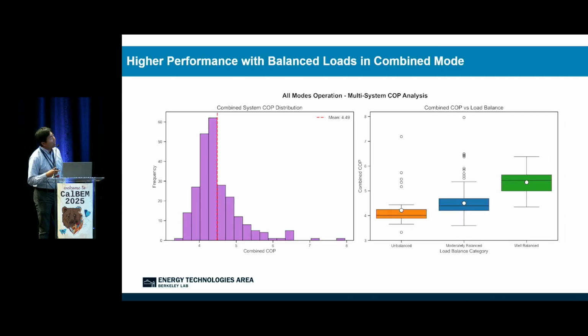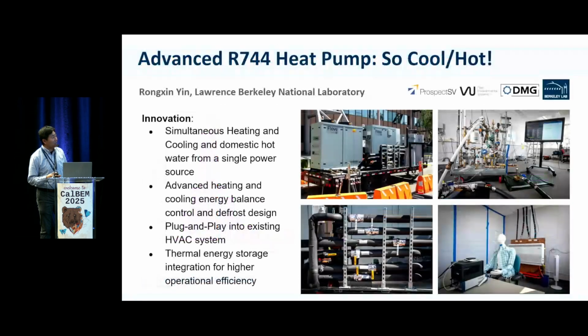And I need to point out, as just mentioned, if you have very well balanced heating and cooling load operation in these buildings, you can have up to 4 to 6.5 of COP, which is very high. It also provides another opportunity: how I can enable the heat pump to run at simultaneous, load balanced operation conditions. So if you can integrate some storage to balance out heating and cooling in a simultaneous mode, you can have very high COP of this CO2 heat pump. All right, that concludes my talk today. Thanks.